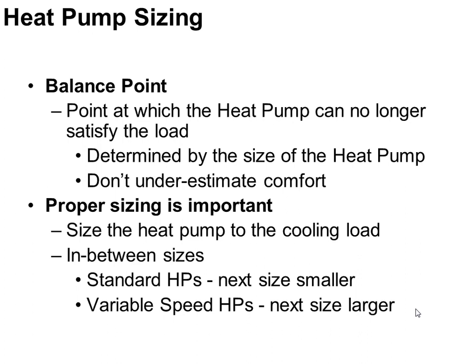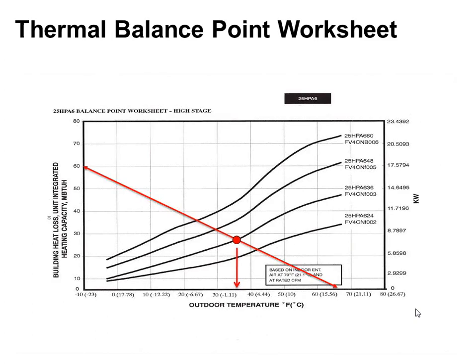So we're going to try to size this more for the heating load and less for the cooling load. Now we can't size it for the full heating load in our climate, just because the heating BTUs are so much greater than our cooling BTU needs. But we're going to try to size it as close to the heating load as we can, to avoid running the furnace as much as possible. So this here shows you the way we used to do these thermal balance points, and I'll show you the way we do them now on software in a minute.